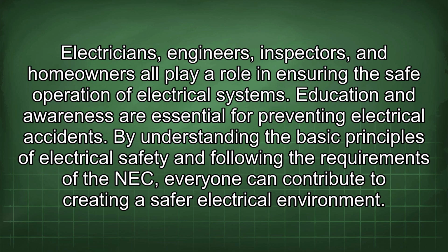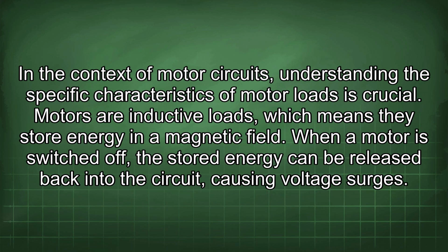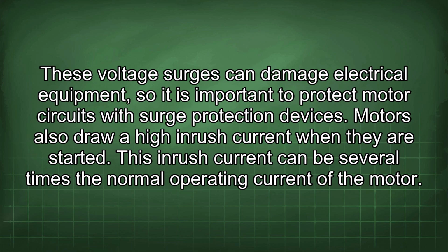In the context of motor circuits, understanding the specific characteristics of motor loads is crucial. Motors are inductive loads, which means they store energy in a magnetic field. When a motor is switched off, the stored energy can be released back into the circuit, causing voltage surges. These voltage surges can damage electrical equipment, so it is important to protect motor circuits with surge protection devices.